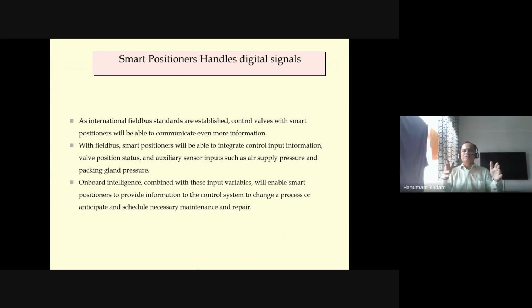If you see the control valve, these are the maintenance areas: packing, gland pressure, glands, and all. Those inputs are available, and any degradation or leakage you can detect early. Onboard intelligence combined with these input variables will enable a smart positioner to provide information to the control system to change a process, or anticipate and schedule necessary maintenance and repairs. So you can plan your replacement based on these inputs. That is the benefit these valve positioners give to the industries.